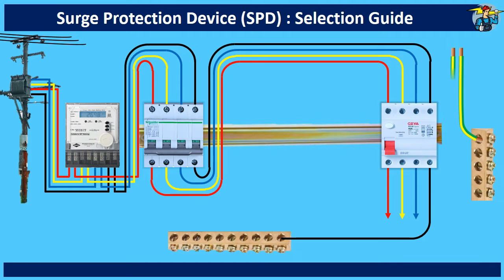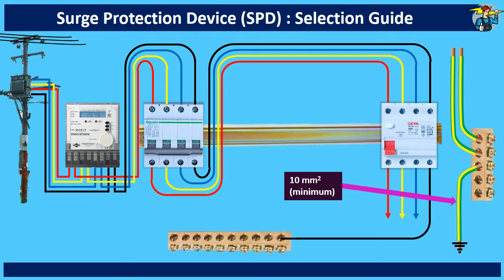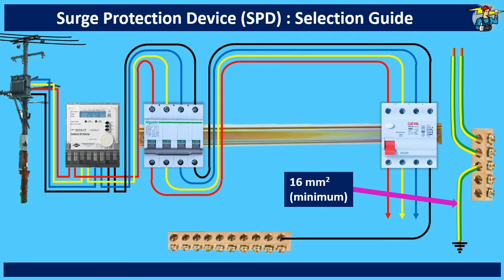Grounding wires from the equipment are connected to the ground connection bar, or so-called earth bar. The earth bar needs to be grounded correctly. If copper wire is used, the wire from the earth bar to the ground rod should have a minimum cross-sectional area of 10 square millimeters. This size of ground wire is preferred for a system with a type 2 SPD. But if this system requires the installation of a type 1 SPD, it requires a copper wire of a minimum size of 16 square millimeters from the ground bar to the ground rod.